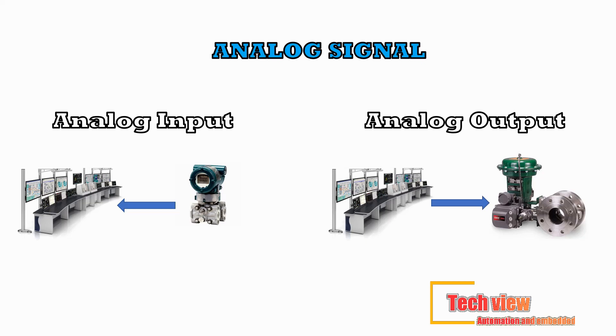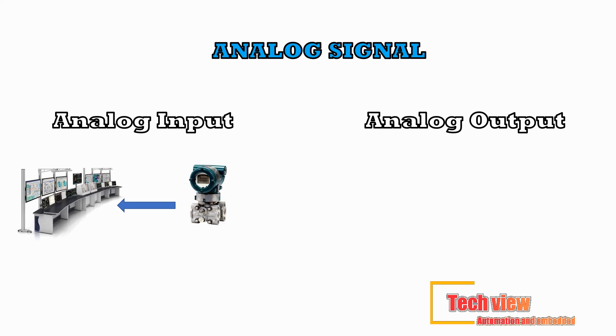If it was a discrete device, it could only be either totally open or closed, but never in between. The source of the signal — an electronic system — can receive power supply via the 4 mA component that is not needed for information transfer. Current to voltage conversion can be done simply by passing the current signal through a resistor and utilizing the voltage drop across the resistor as the converted voltage signal. Reversed conversion requires a voltage to current converter.